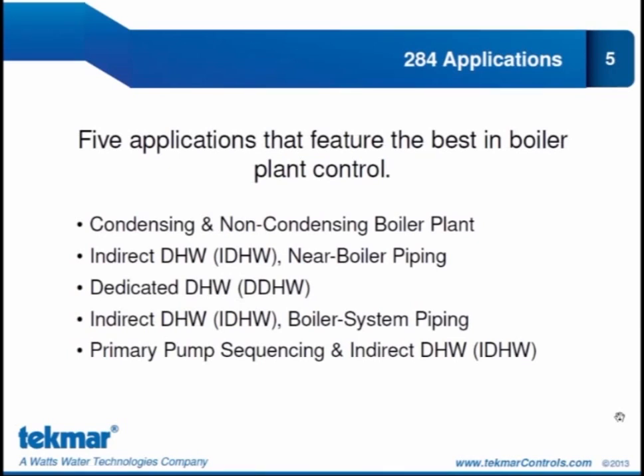The 5 applications that feature the best in boiler plant control include a combination of condensing and non-condensing boilers so that we can really highlight how this control will operate a mixed boiler plant. We're also going to look at domestic hot water generation, both indirect domestic hot water, which we refer to now as IDHW, and dedicated domestic hot water, which we will refer to as DDHW. And this is a distinction you'll have to make going forward: IDHW for indirect versus DDHW for dedicated. Our indirect domestic hot water is specified as either near boiler piping or boiler system piping, and we'll look at that a bit closer as we go through the applications. Lastly, we're going to look at some primary pump sequencing in combination with IDHW, or indirect domestic hot water.